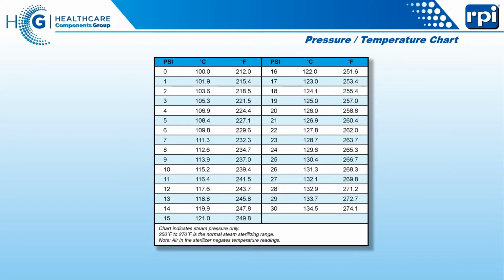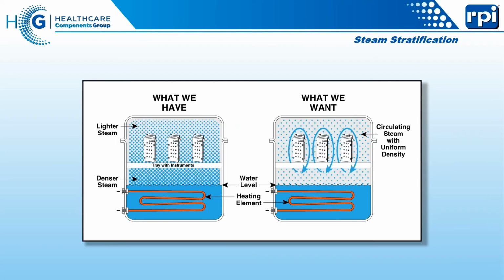In the case of the Midmark sterilizer, we're in about this range: we want to reach 270 degrees and at least 27 to 28 PSI—that's what's built into the machine. If we go above 275 degrees, it overheats. If we go above 30 PSI, it will overpressure, and there are error codes for those conditions in this particular style of machine.